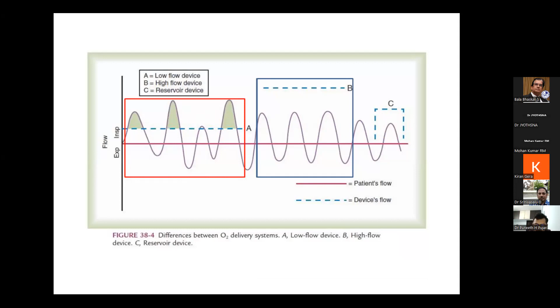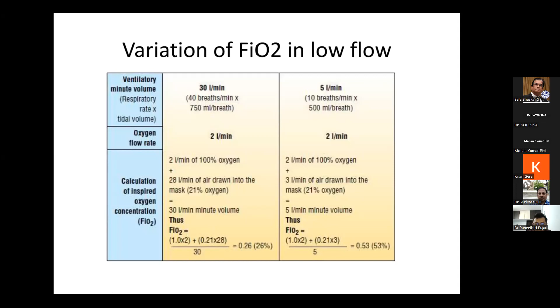When the patient breathes rapidly, compared to a patient with a normal breathing pattern, consider a patient having 40 breaths per minute and generating a tidal volume of 750 ml per breath. Compare this with 10 breaths per minute with a tidal volume of 500 ml per breath, when an oxygen flow of 2 liters per minute is kept. In the patient with the higher respiratory rate and tidal volume, the FiO2 delivered is very low, around 26%, with the flow meter set to 2 liters per minute. But when the same 2 liters per minute is delivered to a normally breathing patient, the FiO2 delivered is about 53%. So the respiratory pattern is very important for the delivery of FiO2.